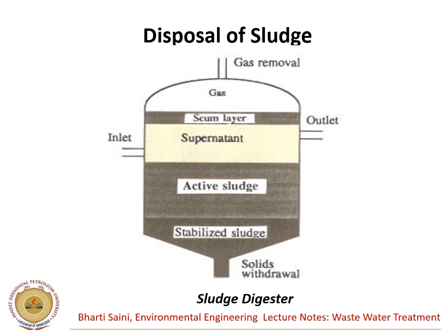This is the final stage of sludge digestion, where more resistant material like proteins and organic acids are attacked and broken up by anaerobic bacteria called methane formers. The organic material and the digested sludge is formed. Here it also produces gases, and the pH is around 7 or 7.5.